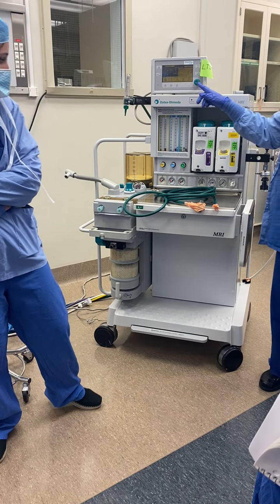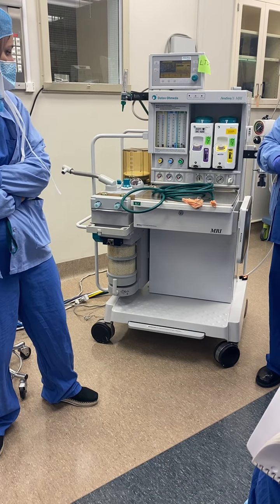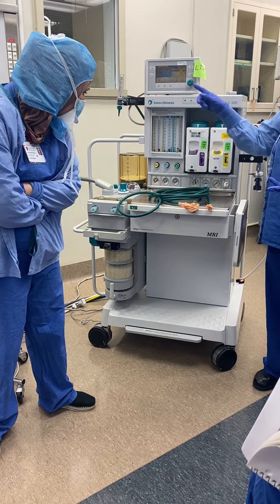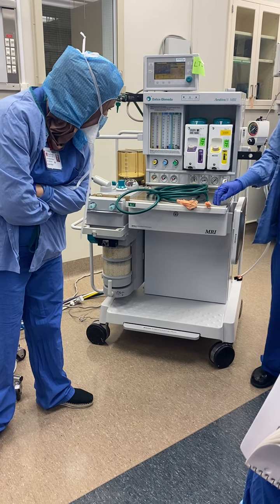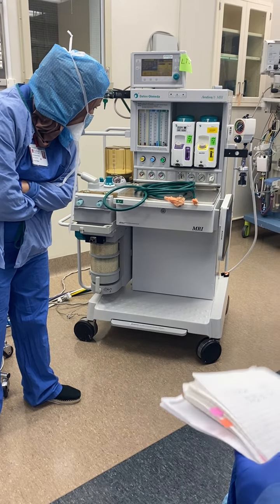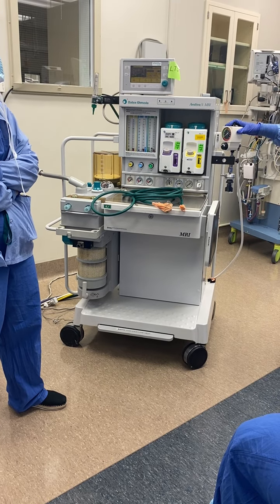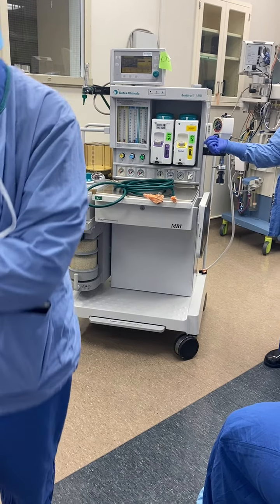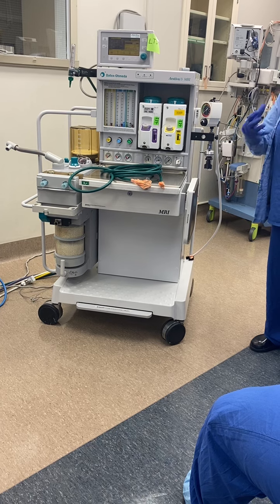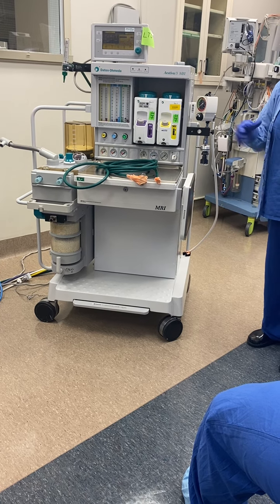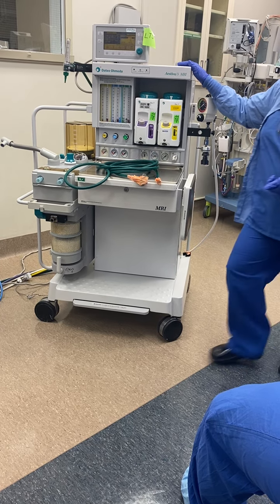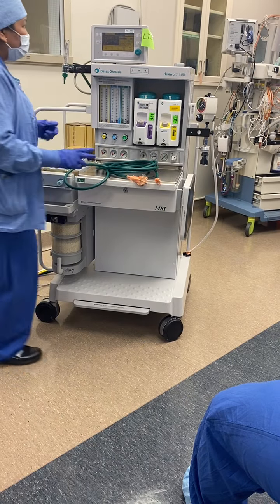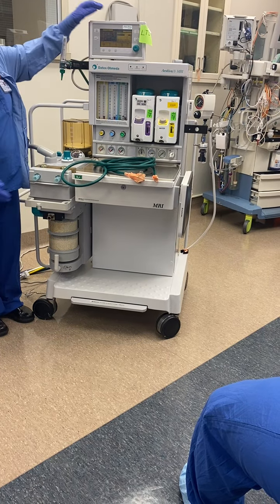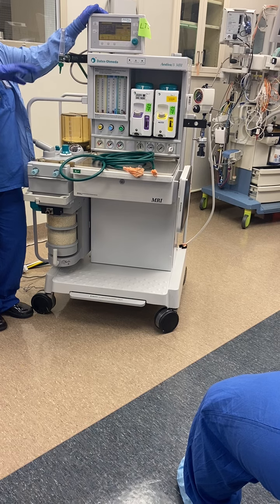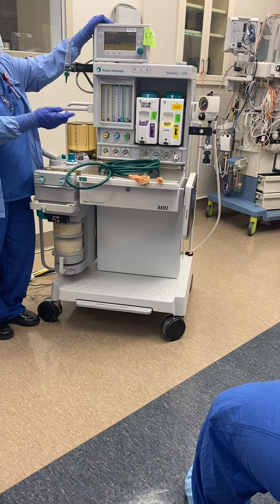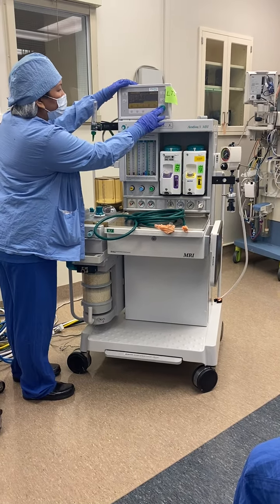It's been alarming this whole time because the oxygen sensor needs to be replaced. The battery is low. That means someone drained the battery, because the battery is only good for so many minutes. So they haven't kept the machine plugged in, and when this was on, it was draining all that battery juice, the internal battery of this machine. So the way that this machine works, you know how you have a button and you self-test everything and you have a leak test? Well, this one, you're going to use this monitor.